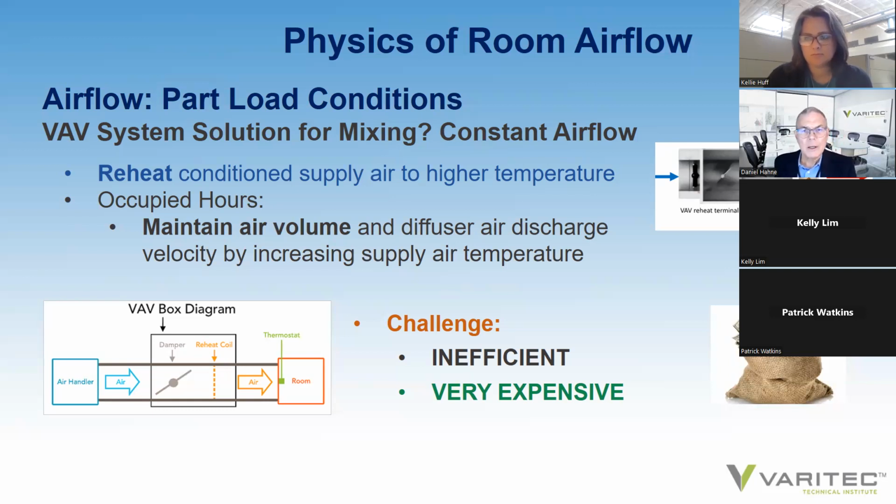And early on, Affiliated Engineers, AEI, wanted to look at a 100% outside air chill beam system versus a medium pressure VAV system. And during the initial budgeting of a mechanical to mechanical comparison, the 100% outside air chill beam system came in roughly $300,000 to $400,000 over and above medium pressure VAV.